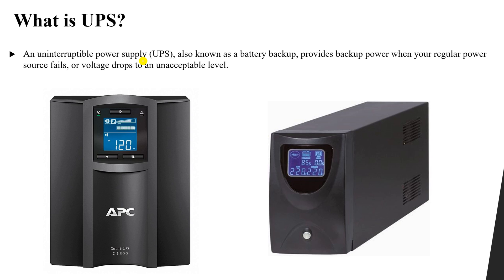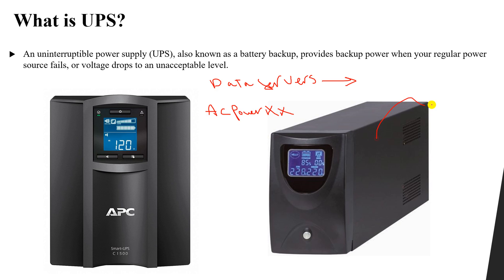For example, if you have some critical loads such as data servers and you would like them to have electrical power all the time, then you will use a UPS. If the AC power fails, it will start providing electrical power in just milliseconds to your data servers, computers, or any important loads. UPS is also used when your AC power has fluctuations, harmonics, or other issues — it will convert this to an acceptable voltage output waveform.